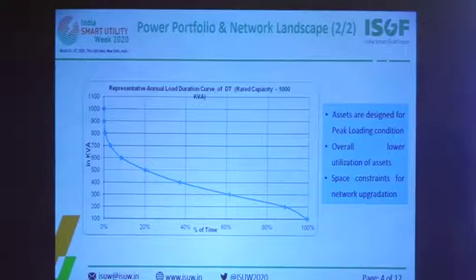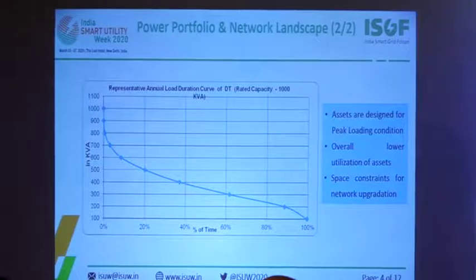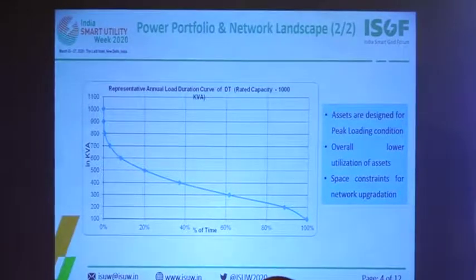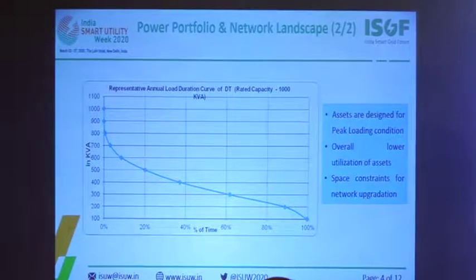This another graph indicates the kind of loading of our assets. This is a load duration curve of a distribution transformer, which shows that for around 90% of the time, my DT is loaded only 20% of its rated capacity. So our assets are loaded way below their rated capacity most of the time, meaning we are planning asset mapping basically for peak loadings. If we can shave off our network peak using energy storage, we can avoid additional expenditure for augmentation of our conventional lines and transformers. That could be one of the use cases for distribution companies.